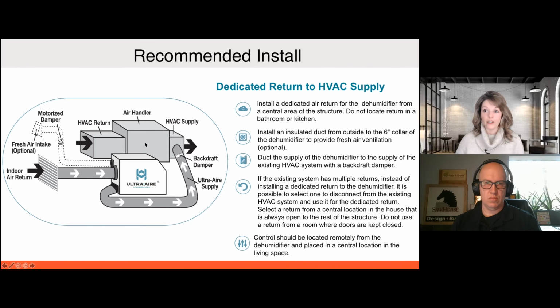So that's the first one. We want that air conditioner when it's running to remove as much water as possible. We are supplemental dehumidification. We are picking up what the air conditioner can't remove when it runs, or when it's not running. That's what we focus on. But we want that air conditioner to remove as much water as possible. So we don't want that heat going over those coils. Second of all, if the air conditioner shuts off and the dehumidifier comes on, again, we're back at what we saw on that SEER slide, that high SEER, that we're blowing that water that's on those coils and re-evaporating it back into the living space. So again, that's the Florida Solar Energy study. I can definitely send it to you, Matt, and you can have that in the links as well, so people can read more about that.